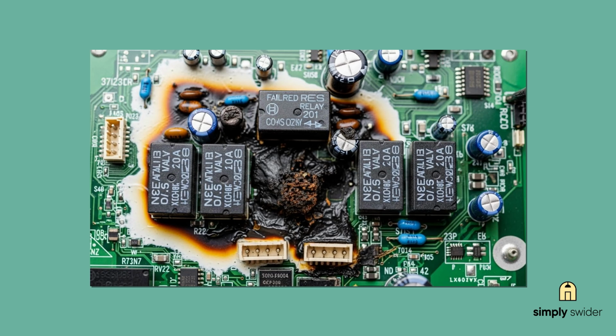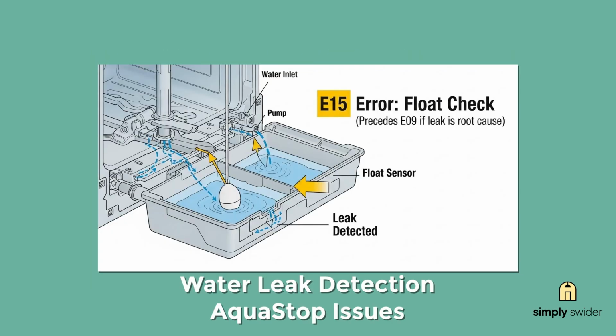The tricky part is this one's tough to diagnose without swapping parts. Your clue that it might be the board is when E09 persists after you've confirmed the heat pump and wiring are good. Try a power reset first. Unplug the unit for at least 5 seconds and see if that clears any electronic glitches. If the error comes right back and you've ruled out the pump and wiring, you're probably looking at a control board replacement. Here's one that catches people off guard.